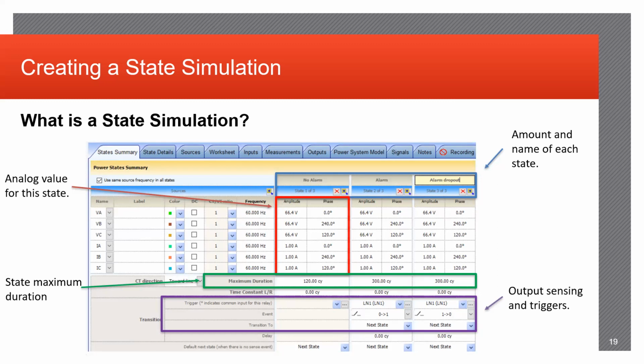So creating a state simulation is, again, extremely important when you're testing the protection logic in the relays. The state simulation actually looks somewhat similar to your control panel. You set all your parameters, such as your voltage readings, current readings, the maximum duration of the cycles, and any outputs that may be manipulated during the test. So in this case, let's say we're testing just a simple output contact from the relay. Usually, say it's a trip contact, and you want to correctly identify that the correct output contact from the relay is picking up when need be. You'll set up your nominal values here, set up a set of fault values in your second state, and then return them back to nominal to indicate that the test is done.